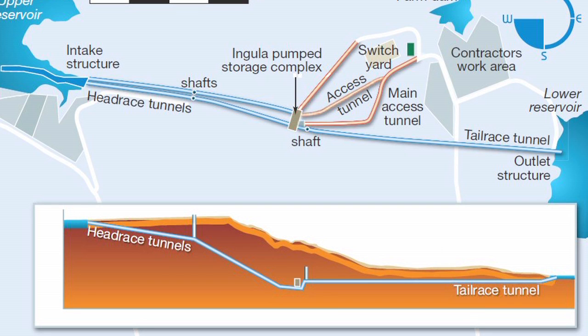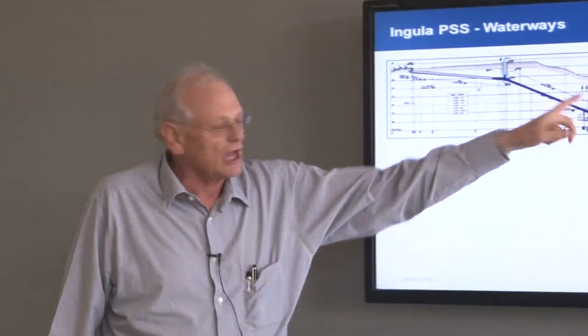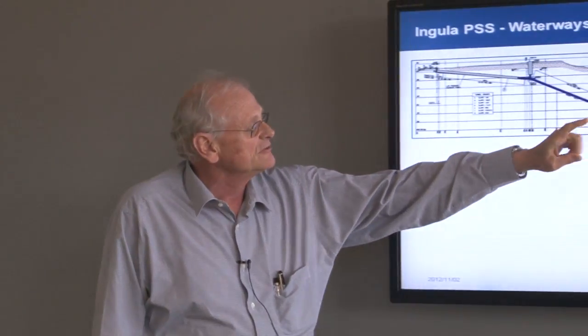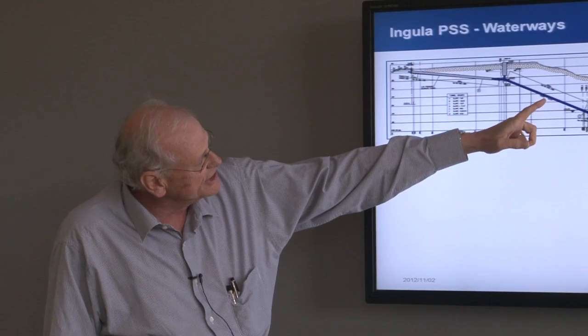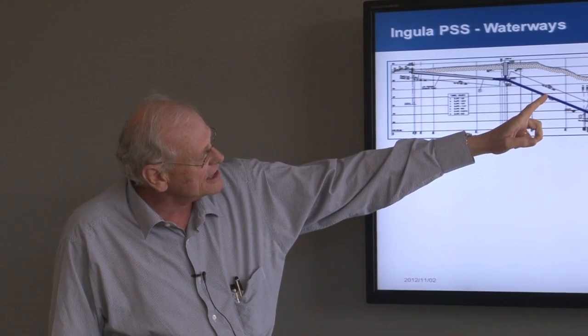Waterways, typical cross-section. The first part is 6.6 meter in diameter, two tunnels, concrete lined. Then it changes into steel lining all the way to the powerhouse. The reason why: theoretically, you need a steel lining if the internal pressure is more than your in situ rock stresses by a certain margin, and I will come to that margin. Using that philosophy, we probably needed a steel liner around about here in the center.